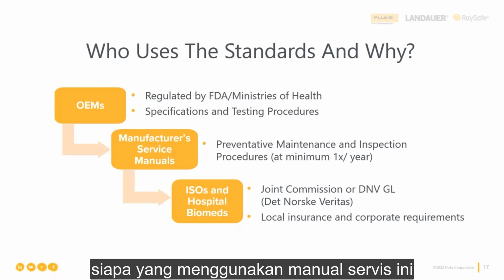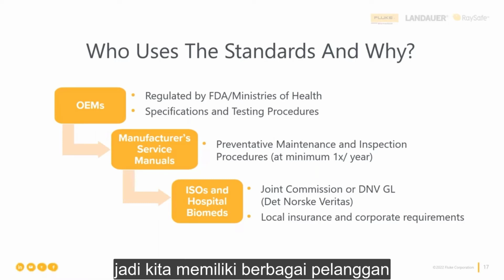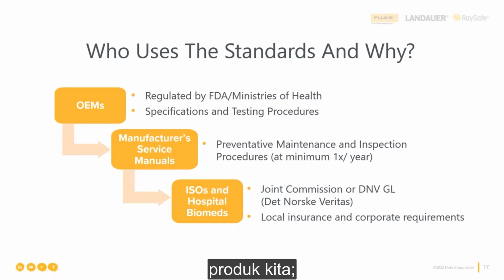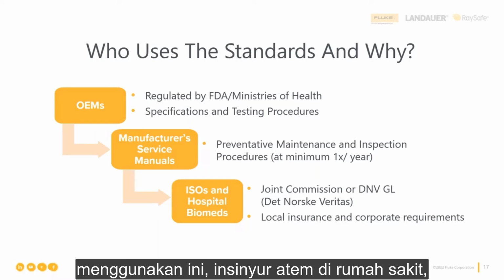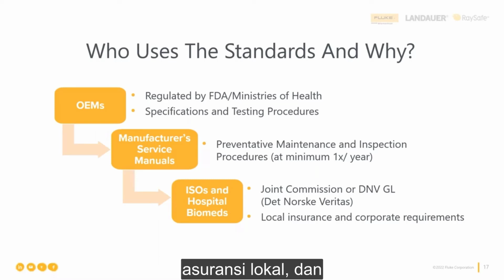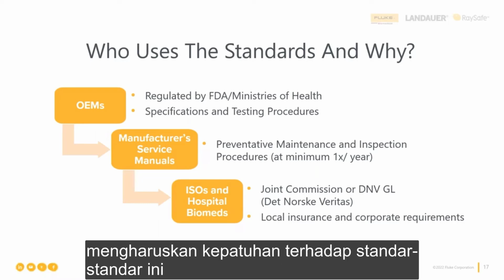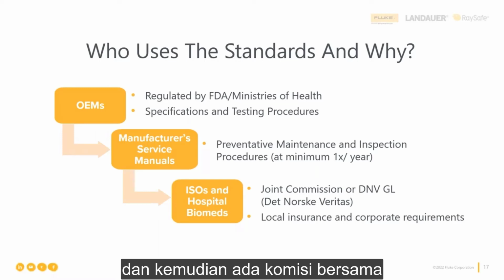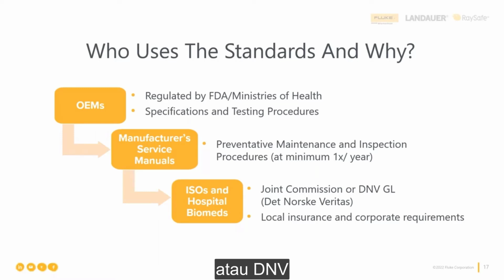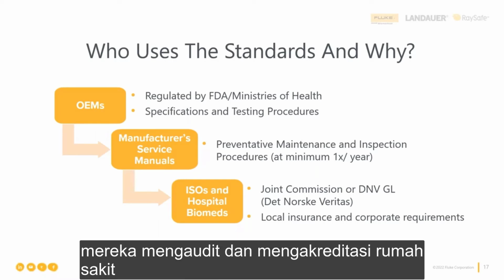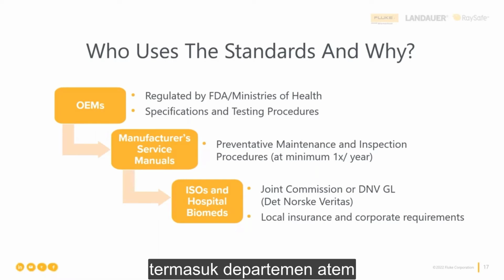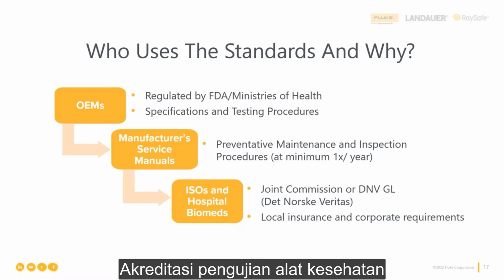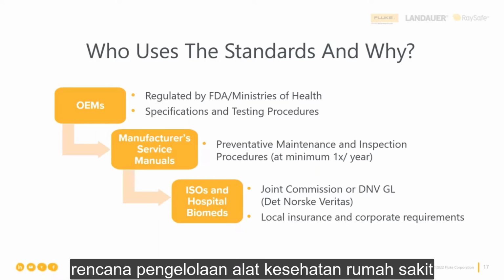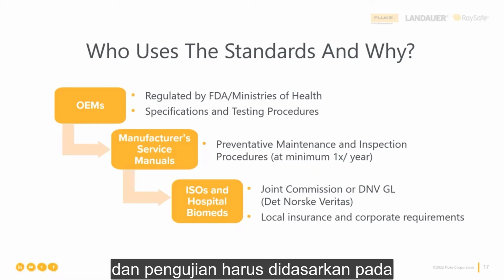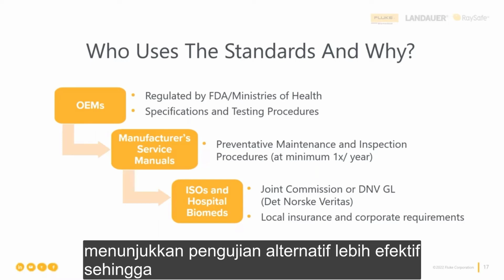The other thing is who uses these service manuals. We have various customers of our products, but independent service organizations use these, biomeds use these in hospitals, and local insurance and corporate requirements also frequently conform and require compliance with these standards. And then there's the Joint Commission, JC, or DNV, Det Norske Veritas. They audit and accredit hospitals, including the biomed departments. The medical device testing accreditation is based on the hospital's medical device management plan, and testing is to be based upon the manufacturer's recommendations unless other independent objective evidence shows alternate testing is effective.